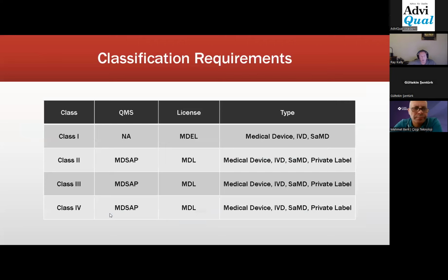Here's the actual classification requirements. For class one, the lowest class, there's no quality system certificate requirement. There's actually no medical device license requirement. Instead, Health Canada requires an establishment license for the establishment that's manufacturing the product, and you can be outside of Canada, for your medical device, IVD, or software. Also, for the distributors that you use, if you're using distributors in Canada, they need to have an establishment license also.